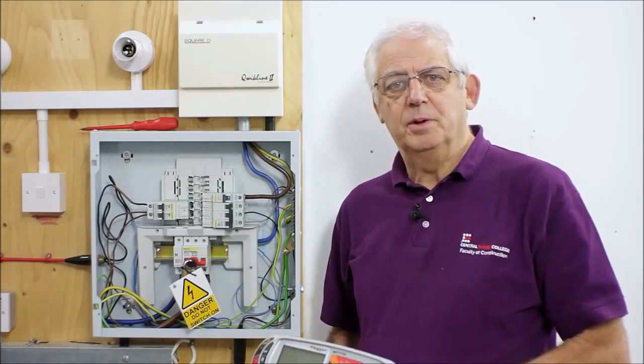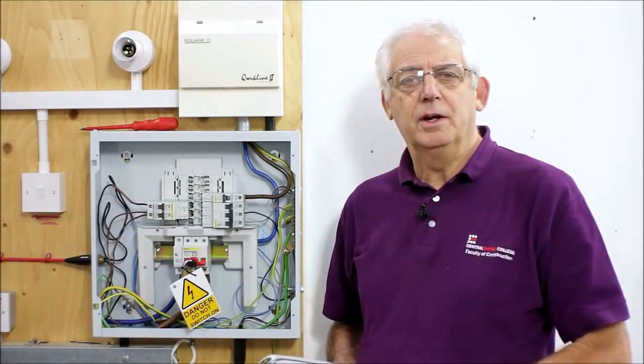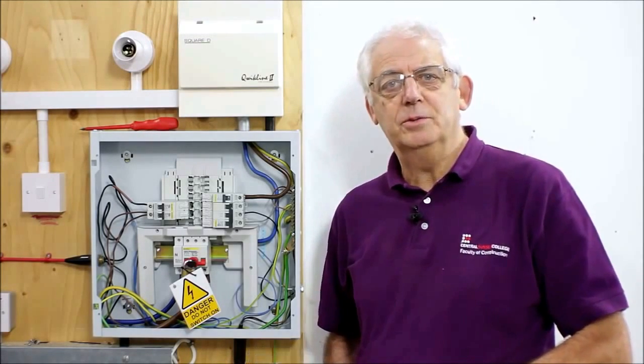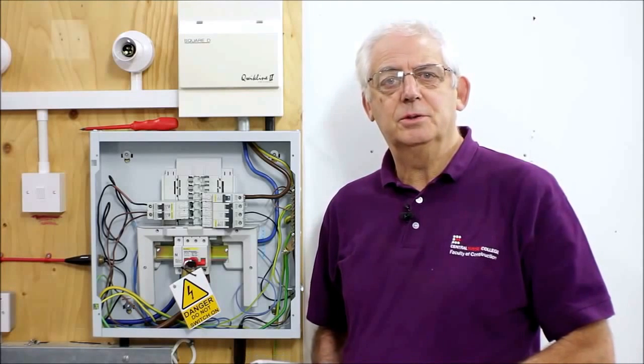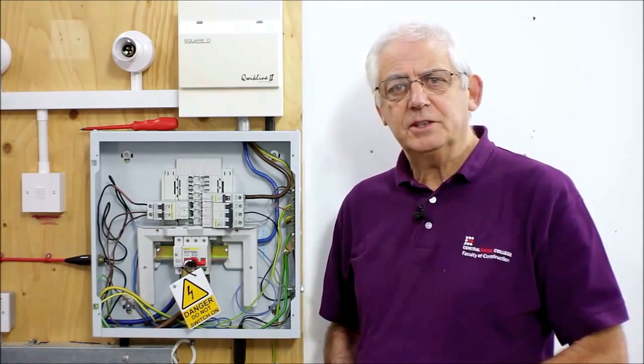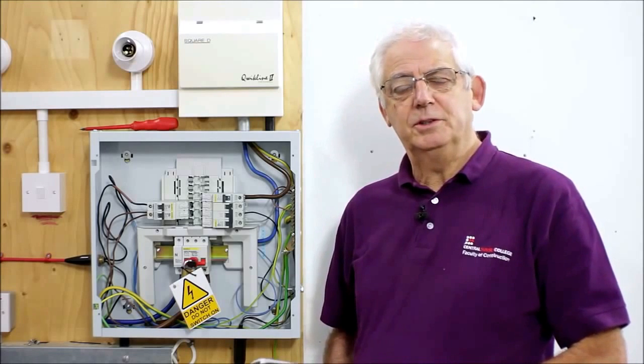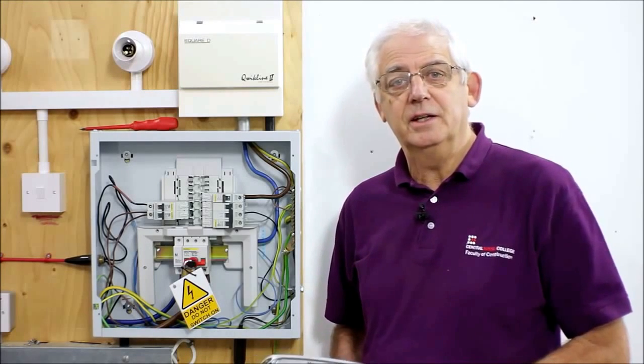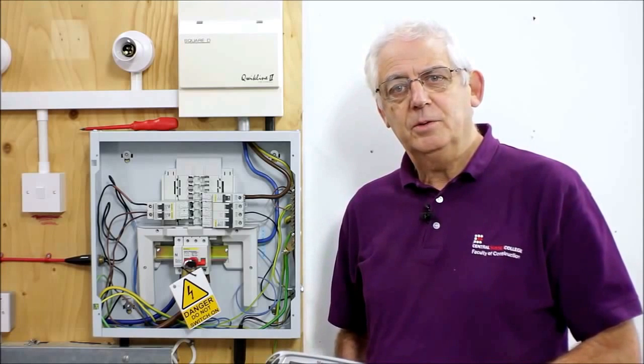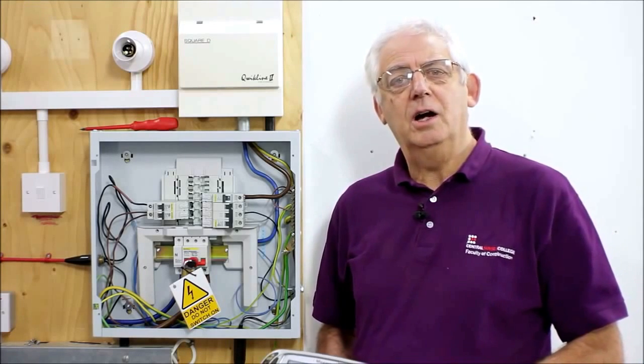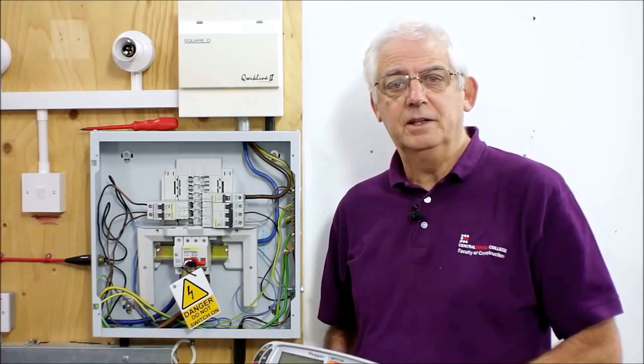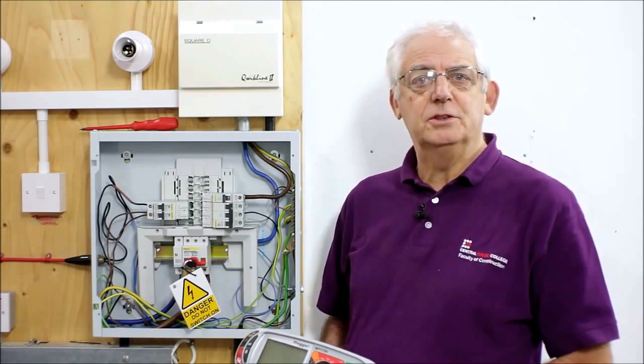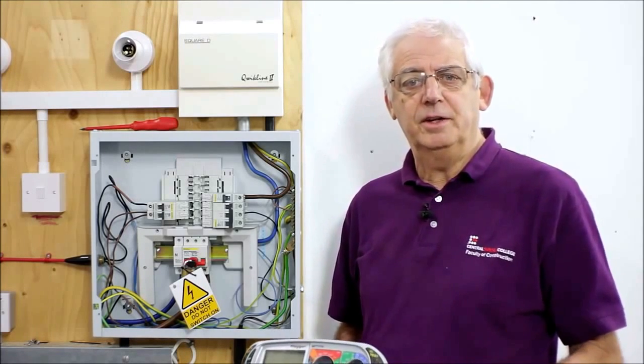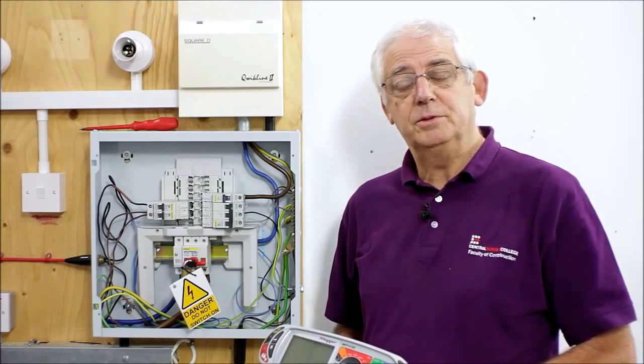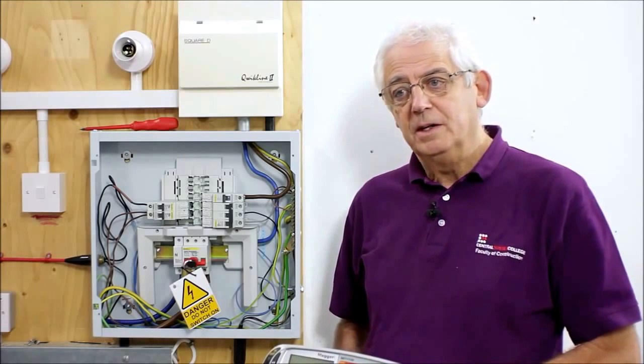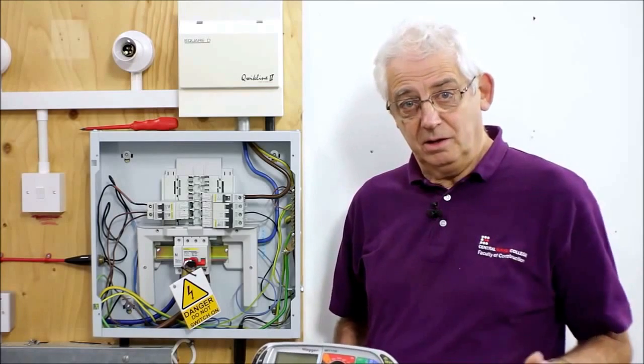Very often you can encounter problems when you're trying to measure R1 and R2 on a three-phase circuit which has a motor starter or a contactor in it. If it's a contactor, it's not too much of a problem because you can just push the contacts together and you'll get a reasonable reading. Where you've got a motor starter which has got overloads in it, thermal overloads particularly, the thermal overloads have got a high resistance wire, so when you take a reading you get a very high R1 and R2 reading, which of course isn't an accurate reading at all. I'm going to show you how I get over the problem.